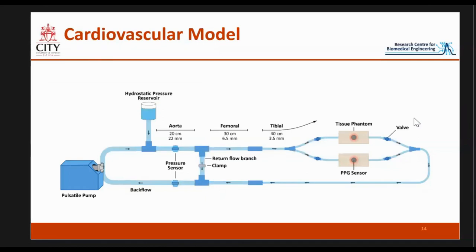Here is an overview of the system as a block diagram. We start with the pump, which represents the heart — we're able to control the stroke volume and heart rate to control the flow rate around the system. This pump doesn't have a reservoir, so we add one to introduce fluid into the system — a simple blood-mimicking fluid. It then leads on to our vascular network, starting from the aorta and going on to the lower body — the femoral and tibial arteries — where it splits at the bifurcation. This is our bilateral system with two branches, and then there's a return flow branch where we can control the pressure into the network.